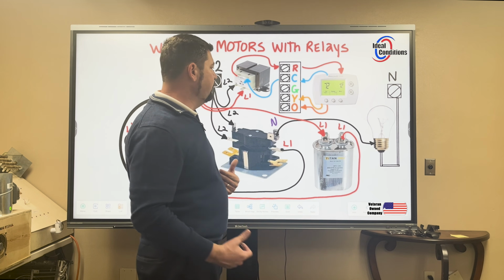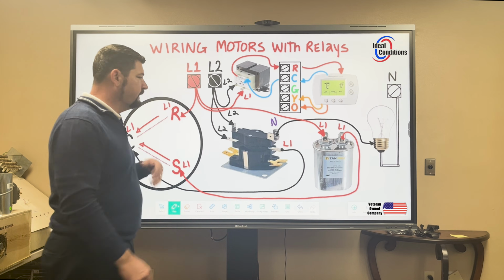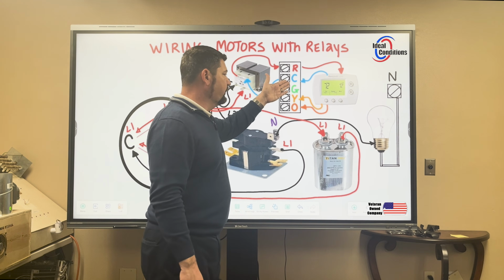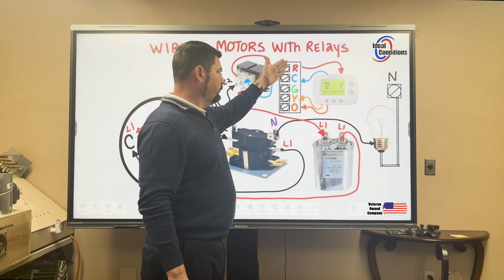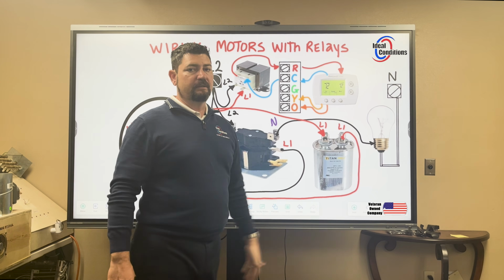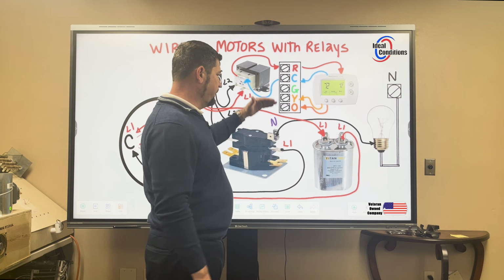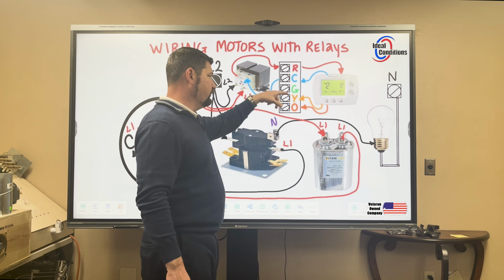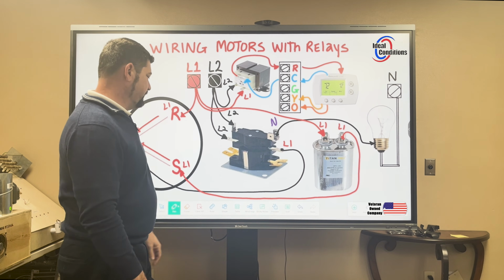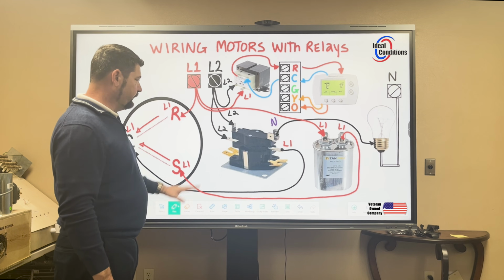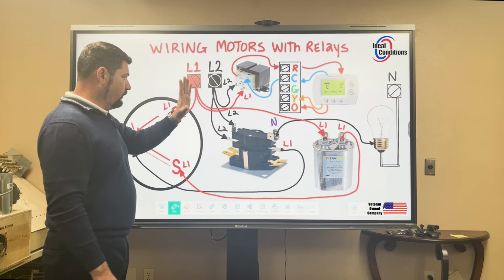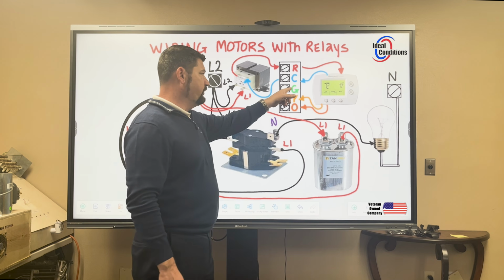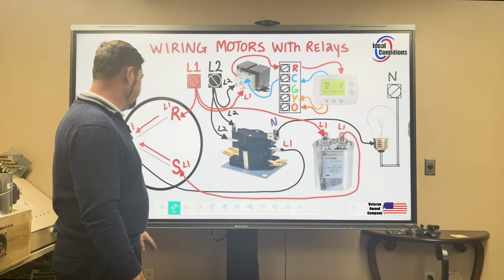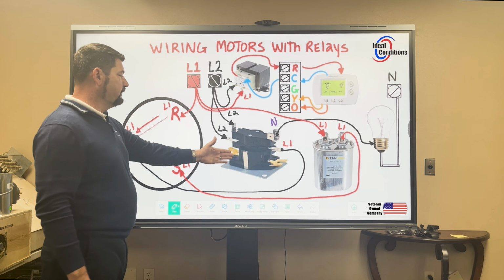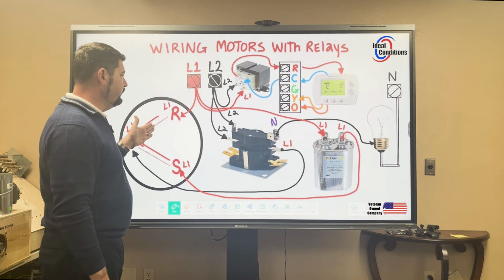As we get into other videos and we start talking about multiple speeds on our motor, like variable speeds and whatnot, these other 24 volts on this terminal block are going to come to light where they're very important, because we're going to have to ramp up or ramp down the motor based on what call we're getting from the stat. In this case, it's very standard. So the only call we're concerned about is a G call to be wired to that blower relay. We're calling it a blower relay because the relay is used for the blower.